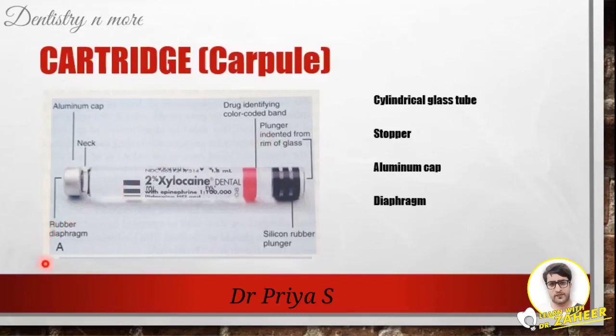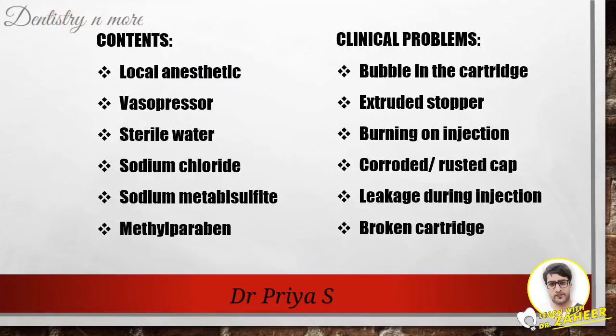The aluminium cap is located at the opposite end from the rubber plunger; it fits around the neck of the glass cartridge, holding the diaphragm in position. The diaphragm is a semi-permeable membrane, usually made of latex rubber, through which the cartridge end of the needle penetrates, forming a tight seal around the glass chamber. Contents of a dental cartridge include: local anesthetic agent, vasopressor, sterile water as solvent, sodium chloride to maintain isotonicity, sodium metabisulphite as an antioxidant to the vasopressor, and methylparaben — a preservative no longer used due to its allergic nature.